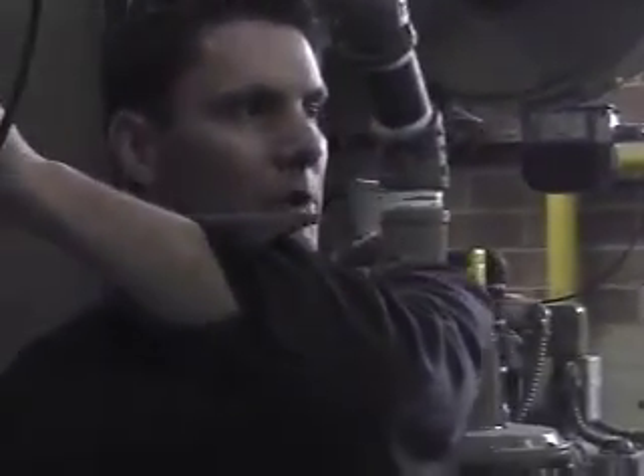What do you do when you check them? You test them, high. Yeah, all you do is just open this up, drop it below where your gas pressure setting is, and then it should trip. It's the same way we can check the high limits. Just lower that below what the water temperature is, it should lock the boiler out. And those specific tests should be done once a year. Like I said, just check your limits.